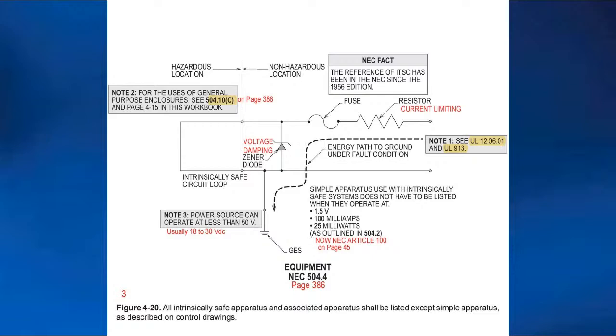And of course, if you're looking now for the definition of simple equipment, it used to be defined in 504.2, but now it's in Article 100 on page 45. And if you do your calculation by 504.10(D) as in dog in the NEC, you can automatically fall within those parameters. You could use a T4 classification for your T code letter. So some of that information is there, and the procedure for using the table is in our design book, volume 2, chapter 21, or you can go look at UL 1203 and UL 913.